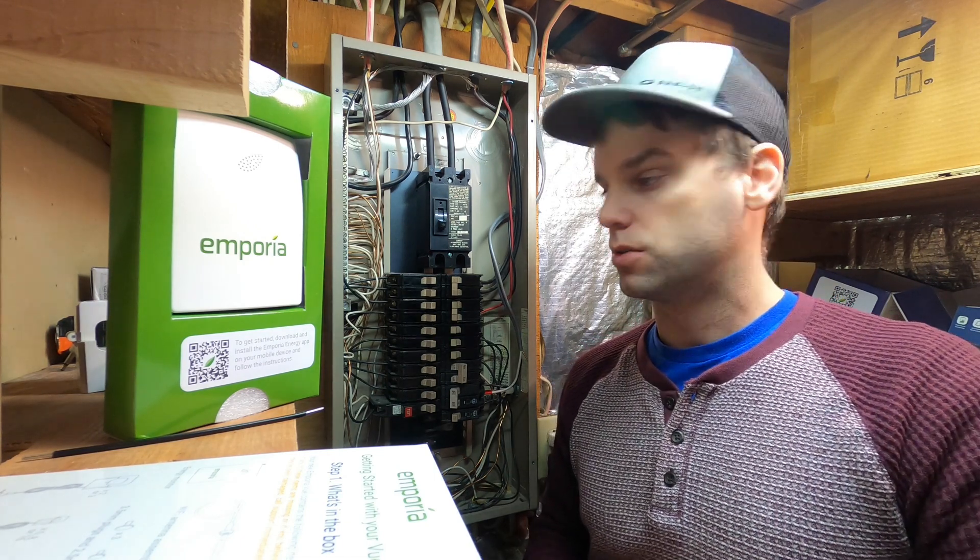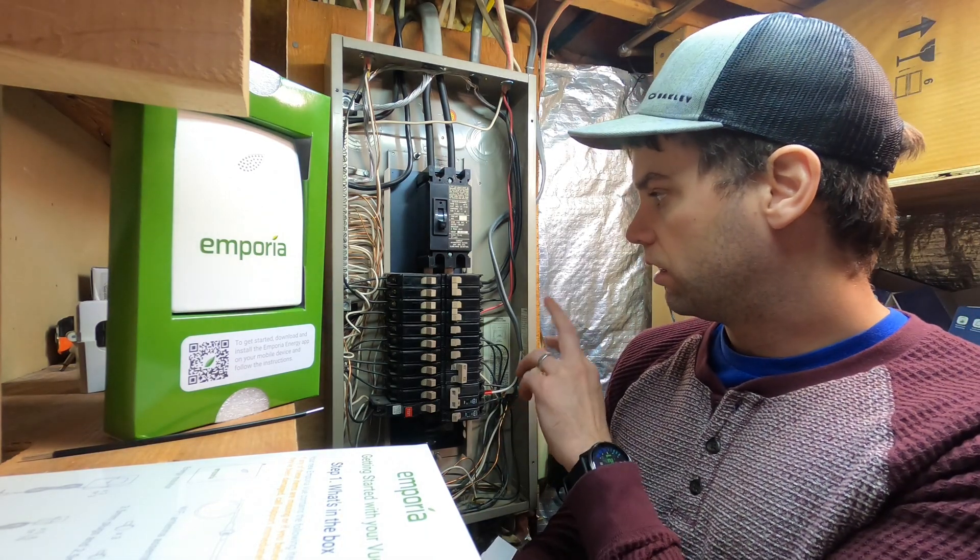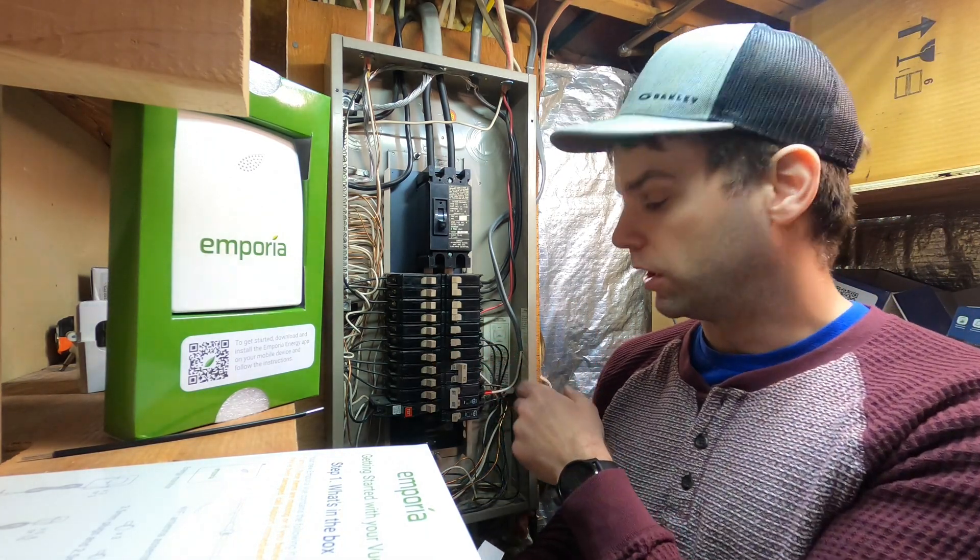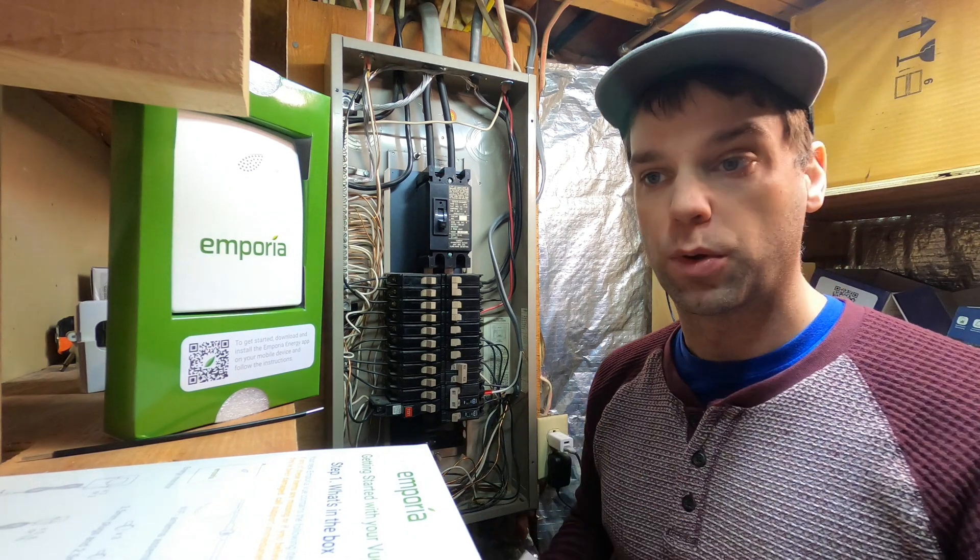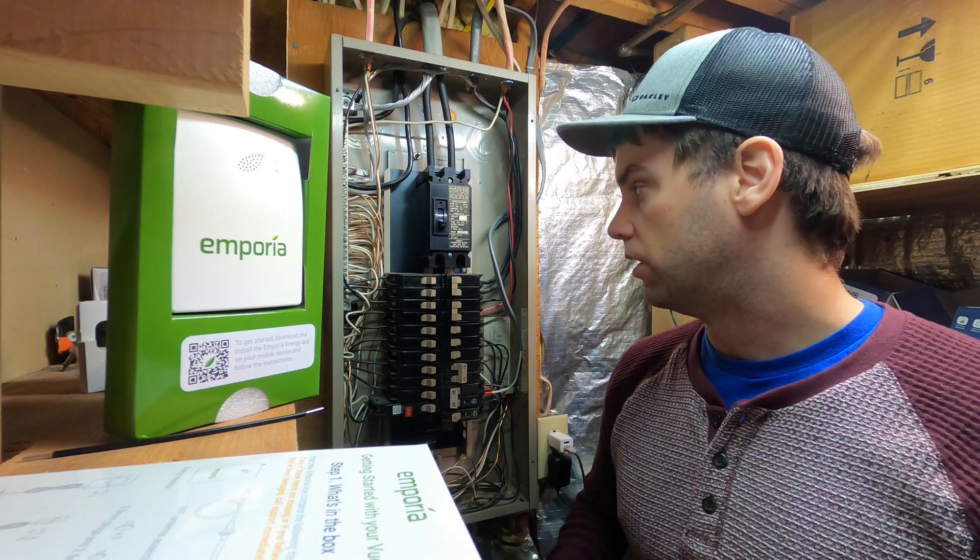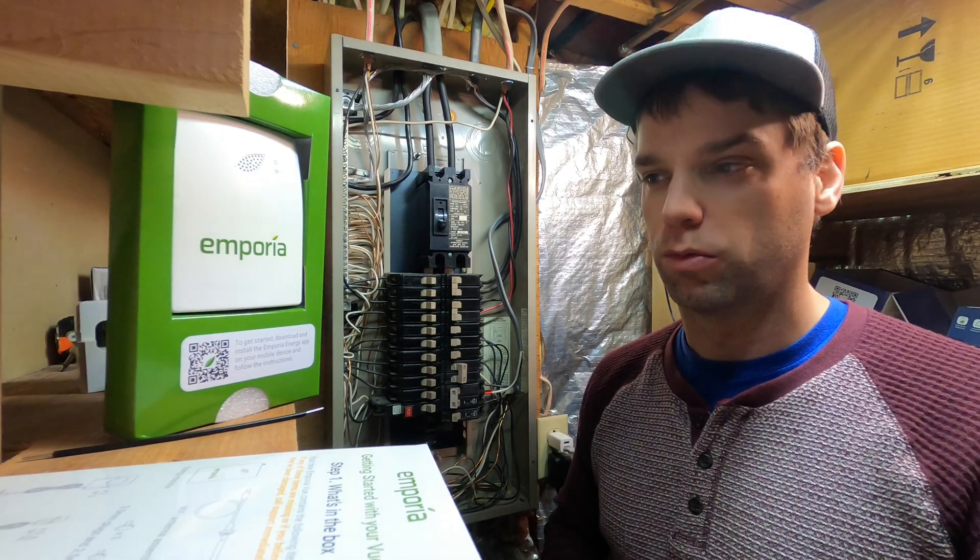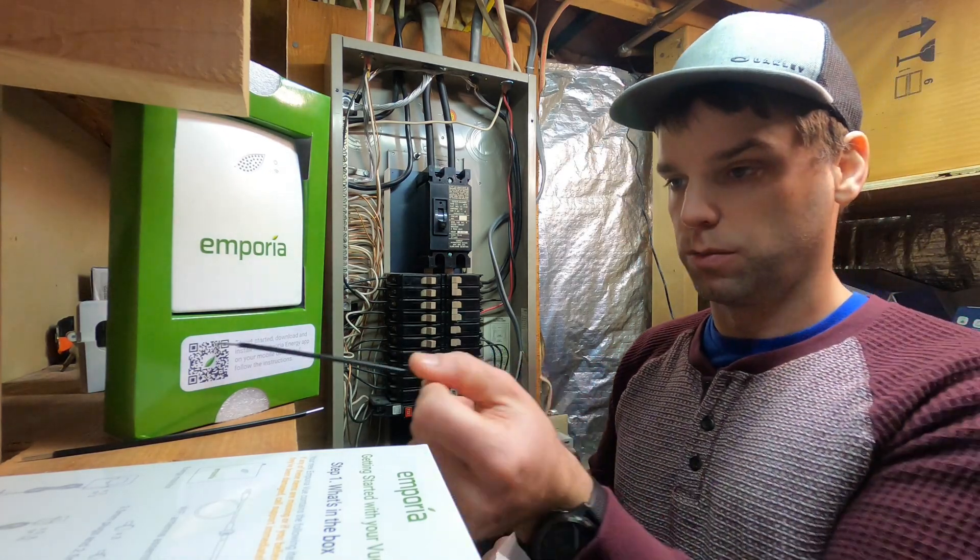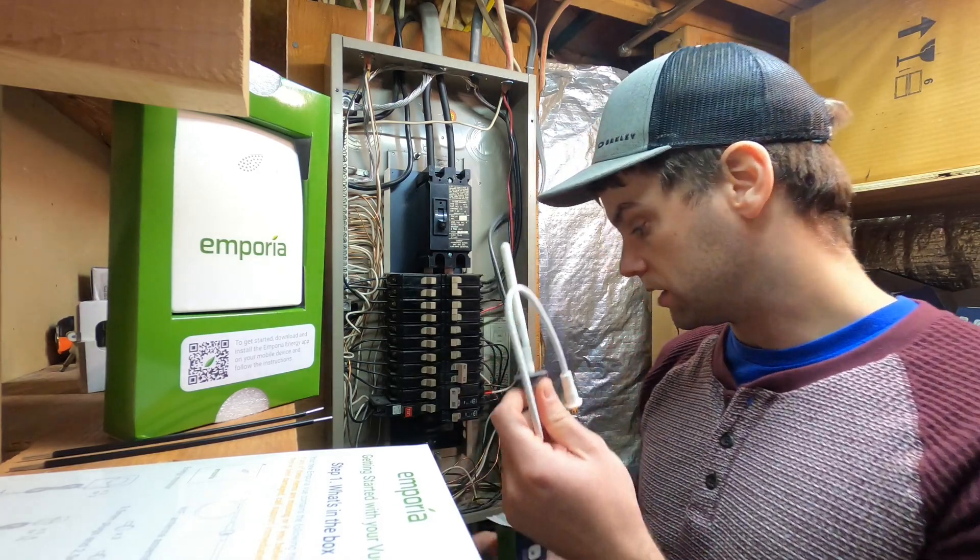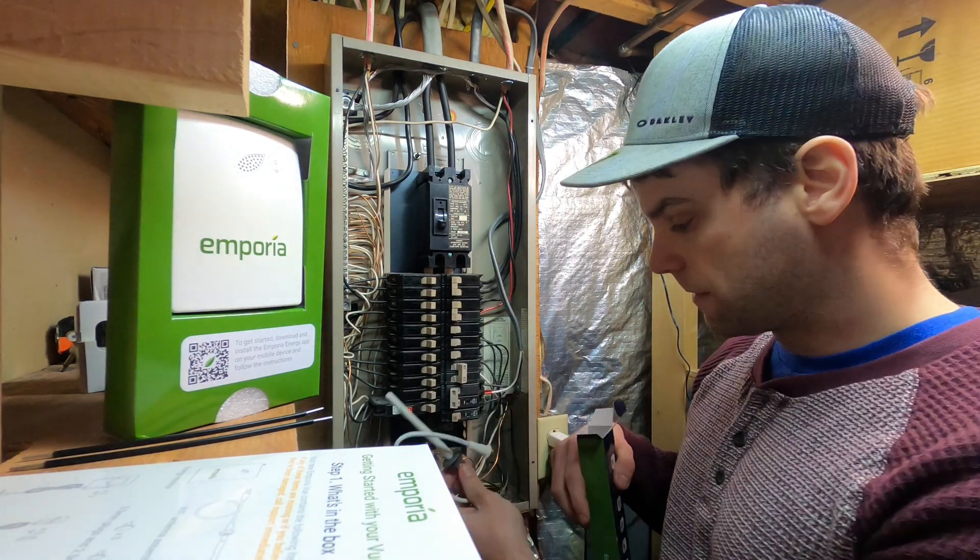Those are going to be used to pigtail to an existing breaker. I'm going to run this off of existing breakers. You do have the option to put two new breakers in and get the voltage on each leg from a breaker, which would be nice because then you could turn this whole unit off without removing the front panel cover. But I didn't feel like spending the extra money for two new breakers that were only going to be powering this thing. So again, pigtail lead. Here's our wifi antenna.